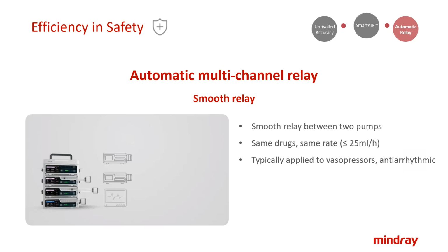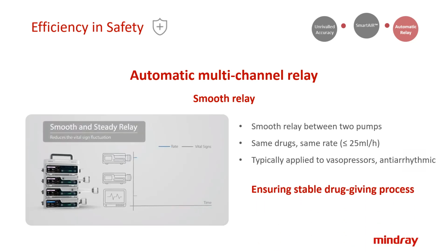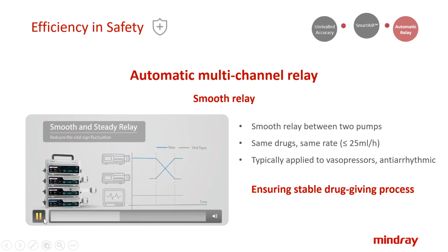So we can have the smooth relay between two pumps. Same drug, same rate less than 25 milliliter per hour, and typically applied to vasopressors and anti-arrhythmic drugs. So how can we perform such relay? As we can see from this video, if the drug on the first pump is already almost empty, then the second syringe pump will start.